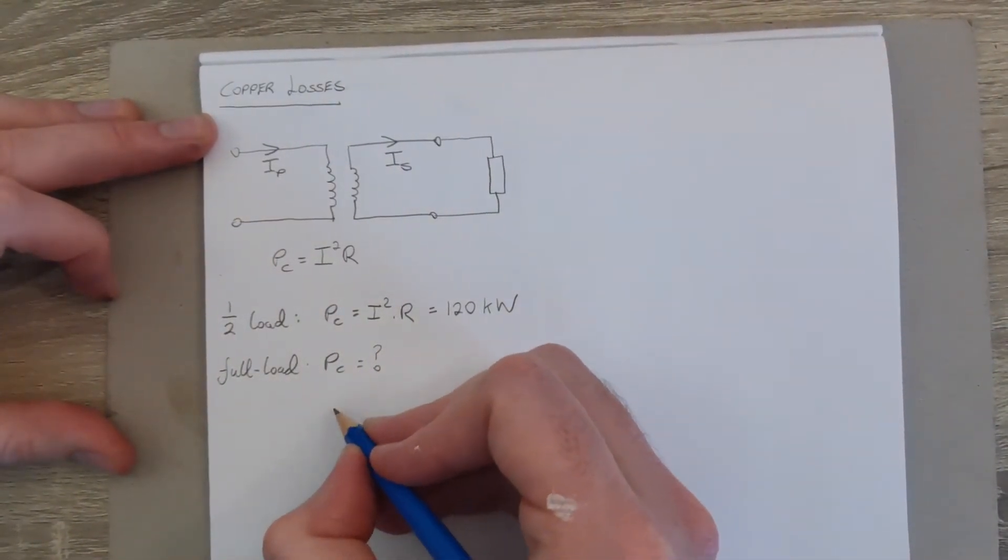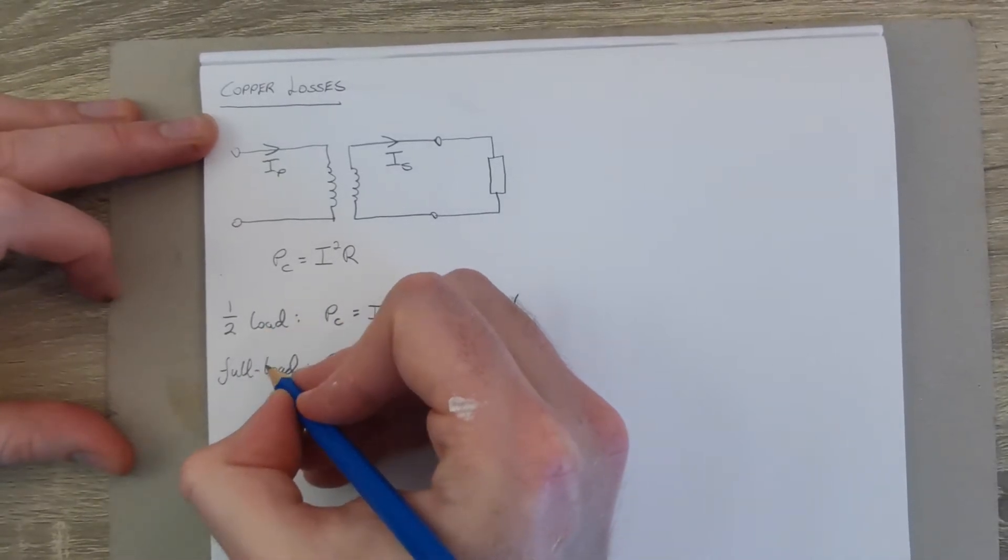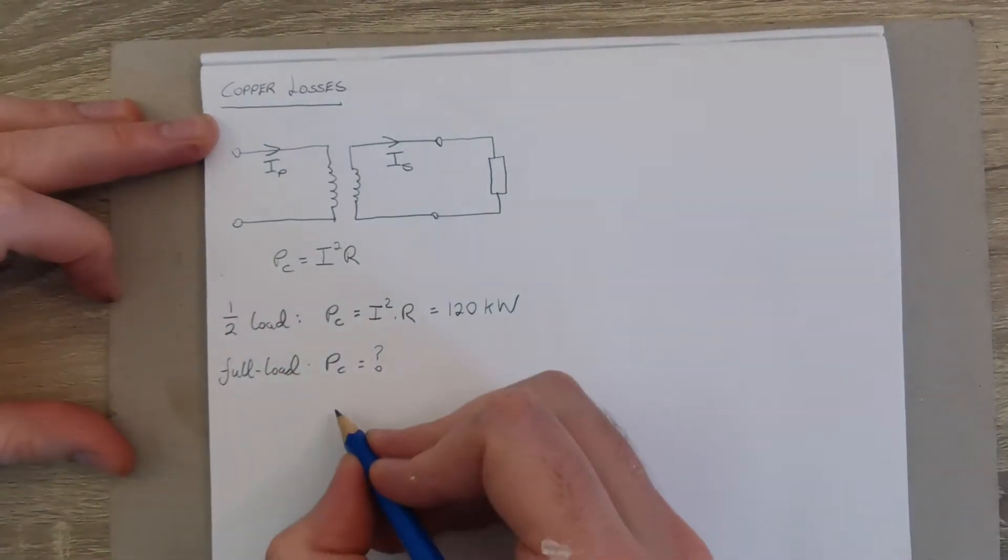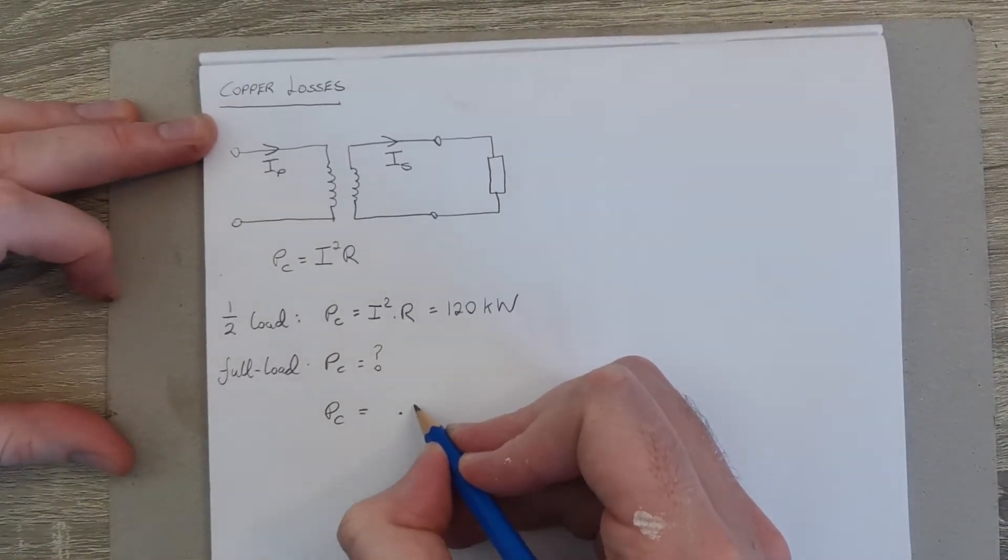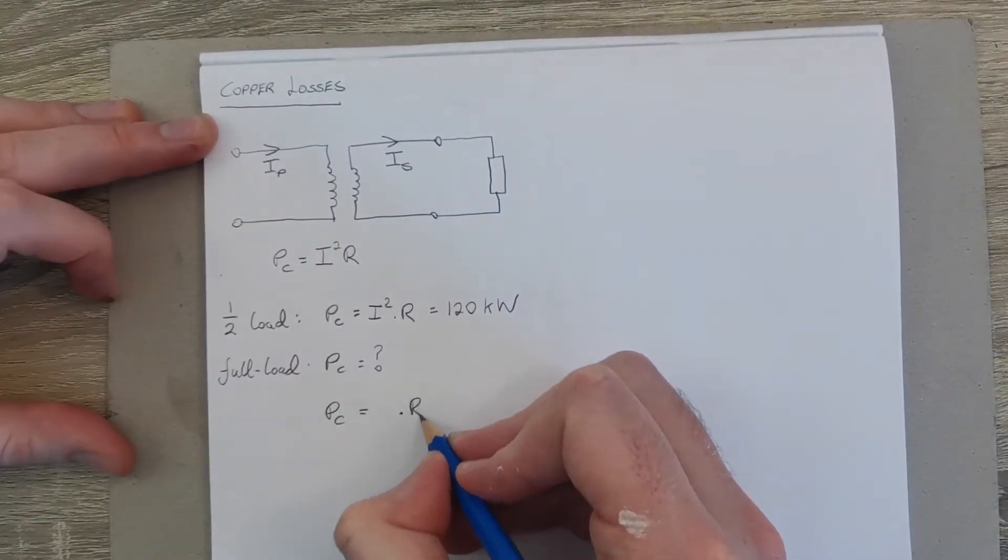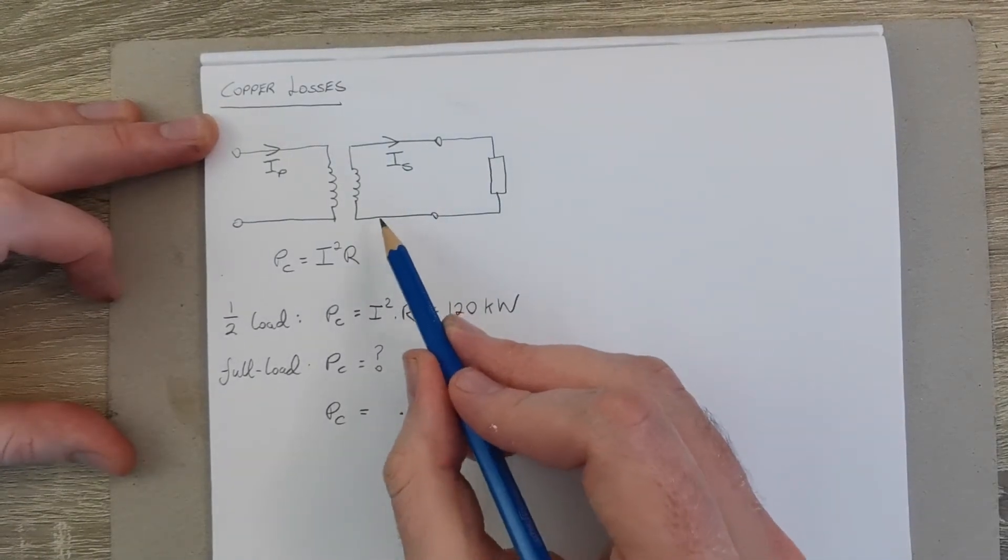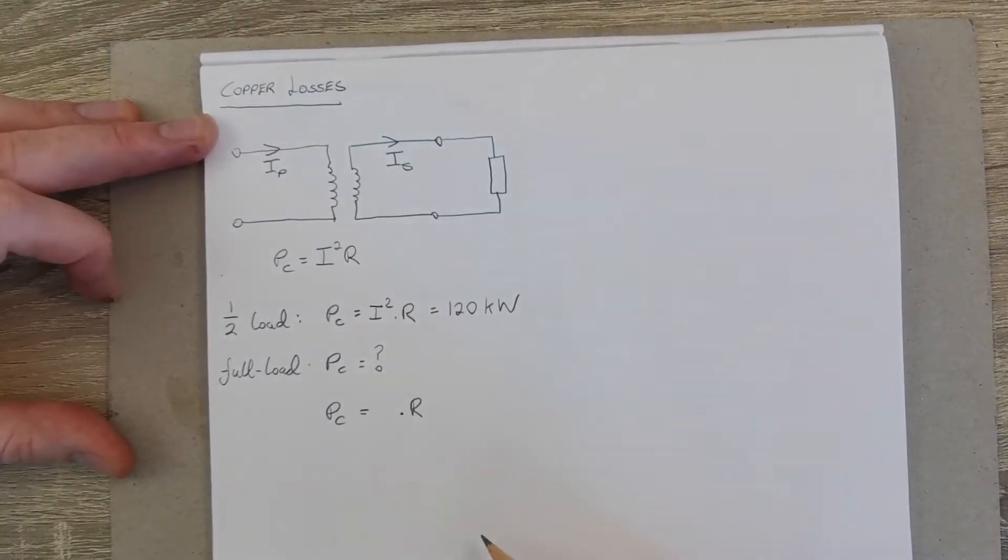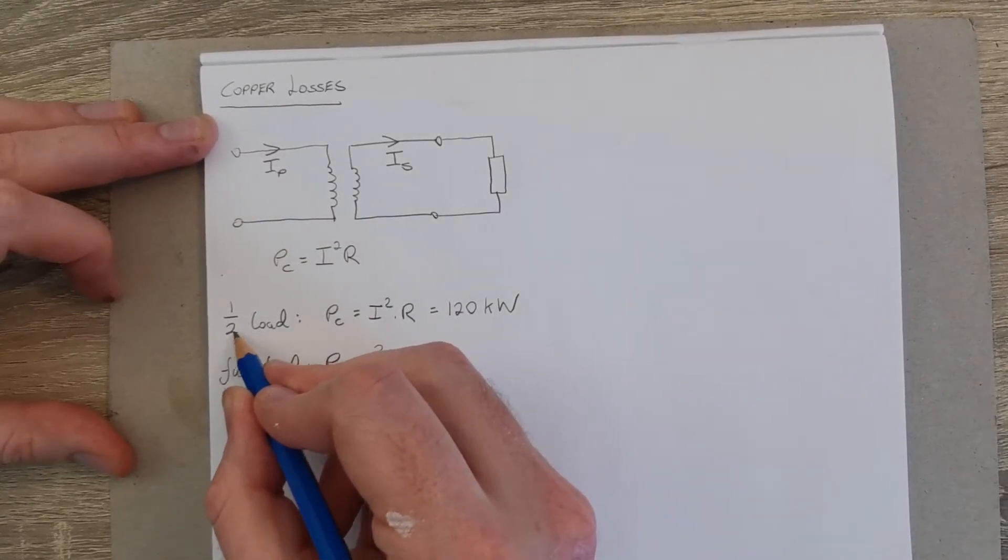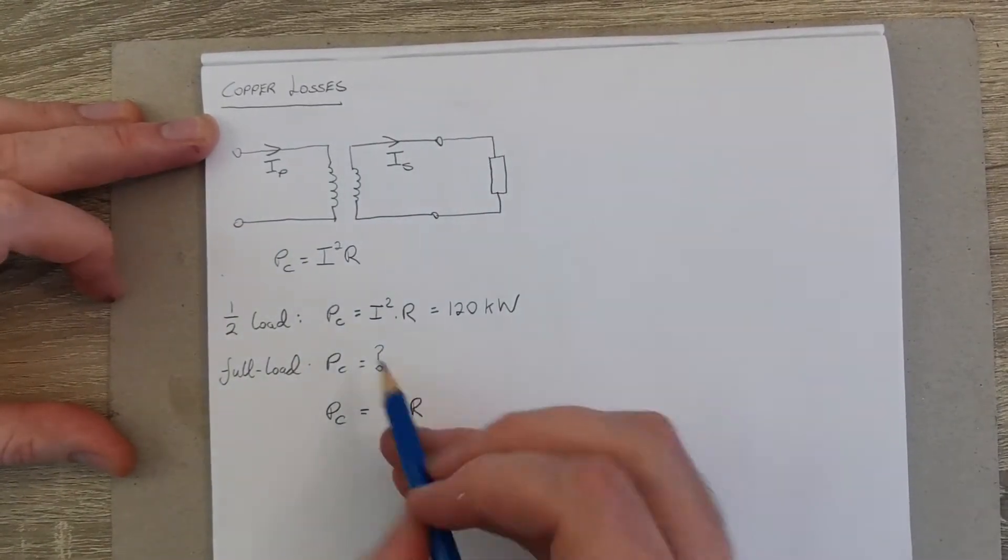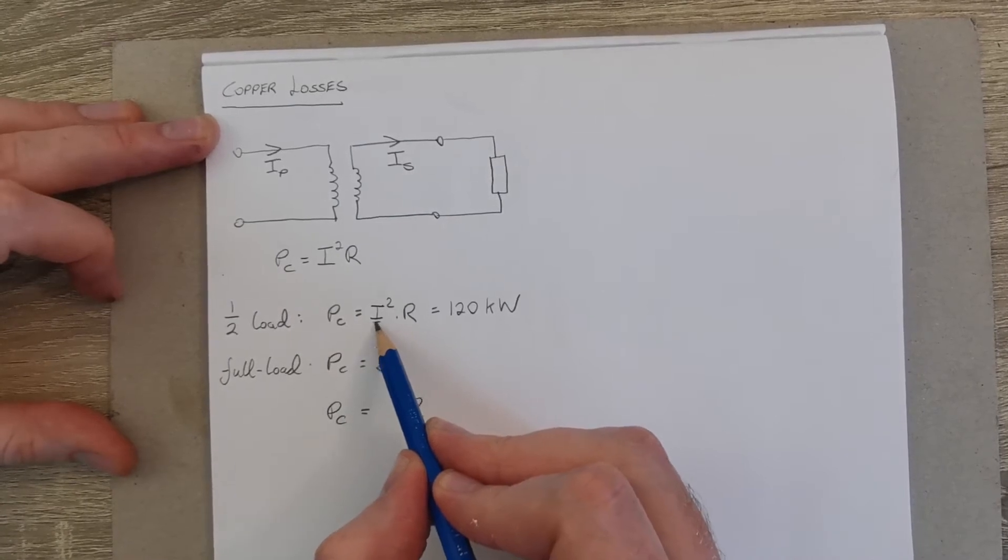So ask yourself what's changed between half load and full load. Well, the copper losses are going to still be dependent upon the resistance of the transformer's coils, so the transformer hasn't changed, it's the same resistance R. But we've gone from half load to full load, which means that whatever current was flowing at half load, now that we're at full load we have twice as much current, 2I, and we still have to square that.